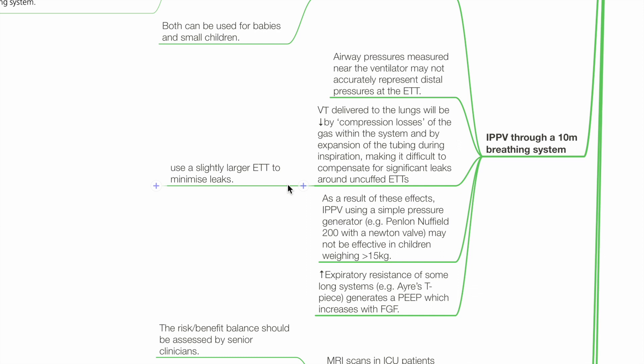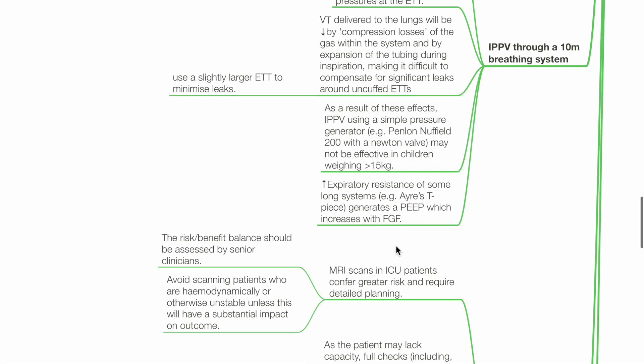As a result of these effects, IPPV using a simple pressure generator such as the Penlon Nuffield 200 with Newton valve may not be effective in children weighing more than 15 kg. Increased expiratory resistance of some long systems such as the Ayre's T-piece generates a PEEP which increases with fresh gas flow.